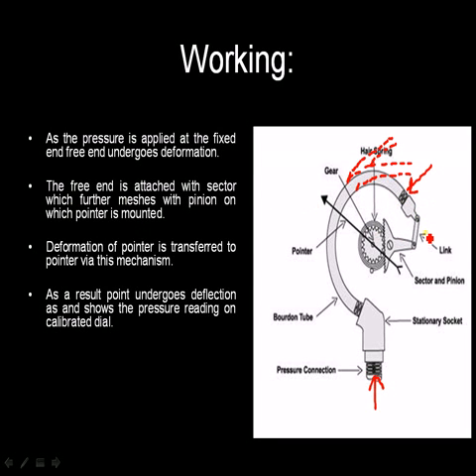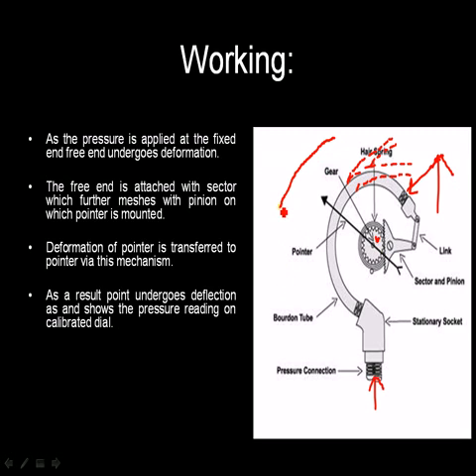Now as you can see, the free end is attached to the link which is further added to this sector. The sector is further meshed with this pinion, and on the pinion, the pointer is mounted. So what happens is this movement of this free end in the upper direction is transferred to the link, which further transfers to the sector. Now this sector, as it is meshed with this pinion, this movement of this free end is finally transferred to this pinion. The pinion undergoes rotation, and as the pointer is mounted on this pinion, the pointer also undergoes deflection.